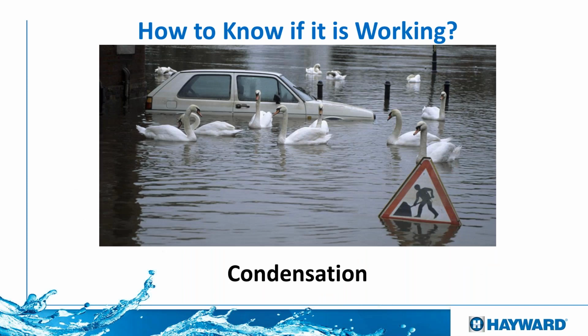Condensation is going to be part of it also. These heat pumps will condensate between 6 to 8 gallons of water. It's all going to depend on the humidity of the area and the temperature of the atmosphere. Same thing with the temperature of the water. If we talk about 80, 80, 80, which is what Roberto said at the beginning, where we have 80% humidity, 80 degrees temperature of water, and an 80 degrees temperature of air, then the heat pump will condensate the most. Remember, between 6 to 8 gallons per hour.